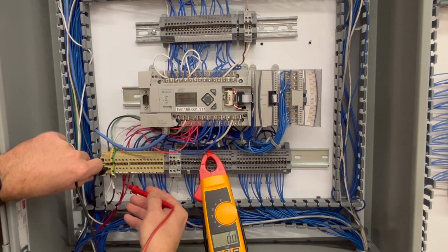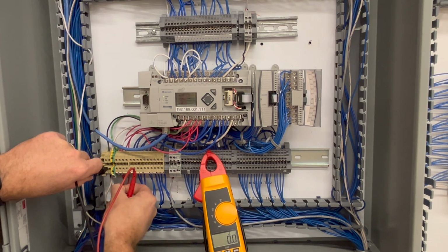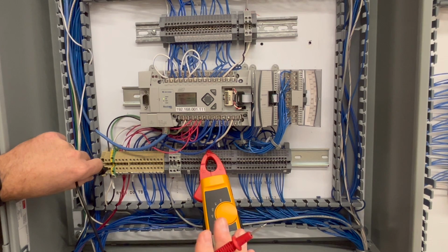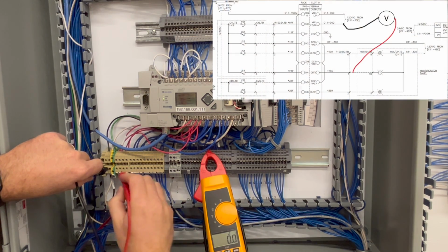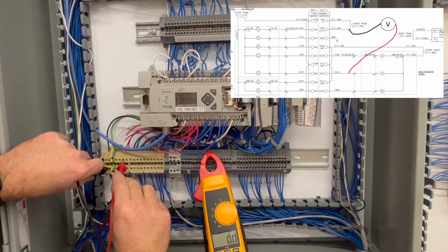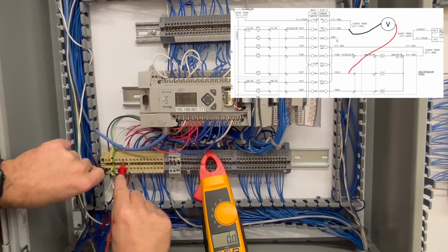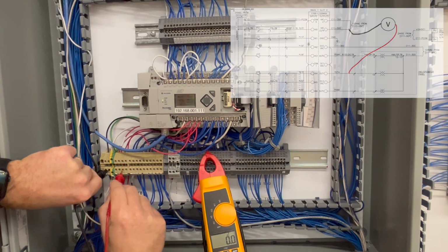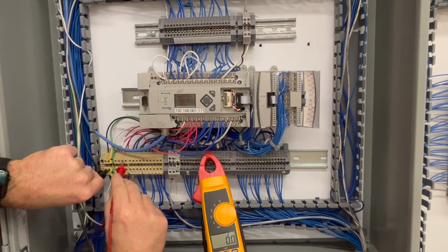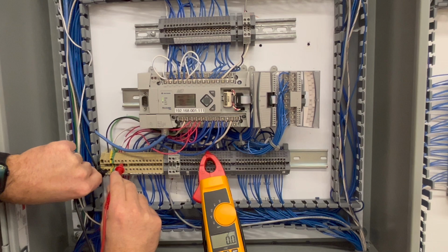So this wire right here runs to the light that we just tested. So we click, we select here, nothing. We have no voltage here. We come here, select this, we have no voltage. So then that means that the problem isn't here, okay? Because if we were getting, let's say, voltage here, but not here, the terminal block would have been cut, which would be very unusual.